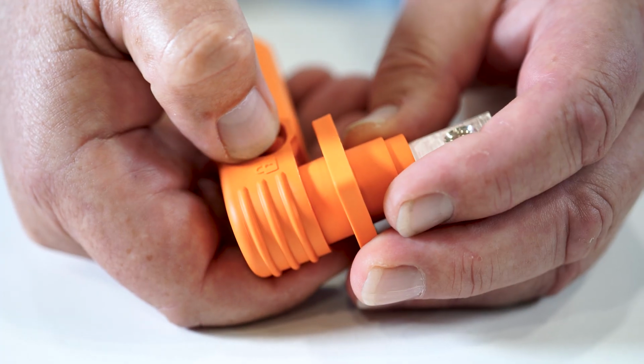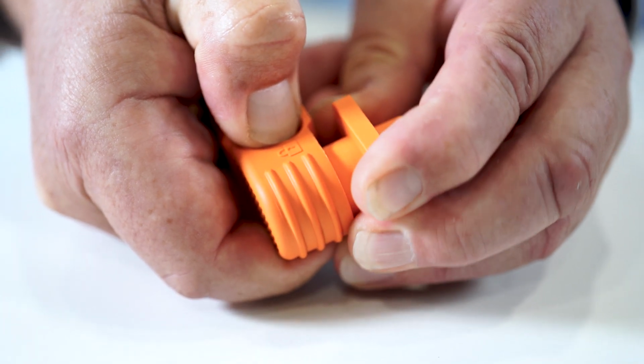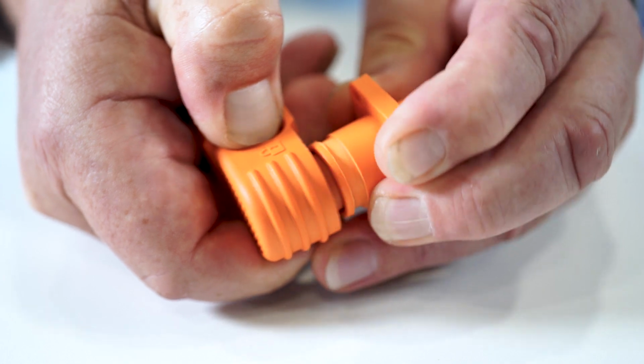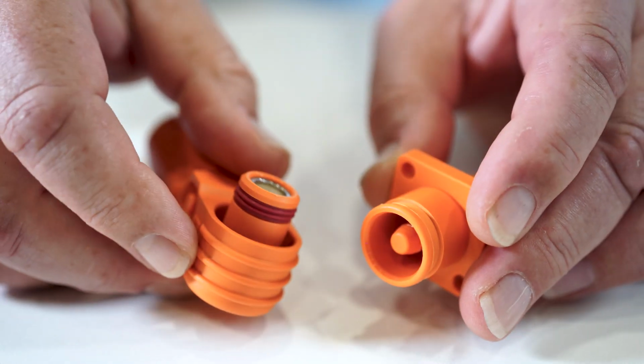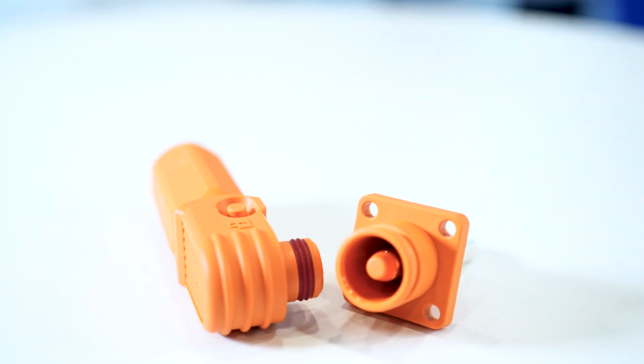Because of the many environments they're used in, the IP rating becomes very important. Some of these environments are quite harsh, where there may be liquids or dust ingress. These connectors are IP65 when unmated, meaning they're completely protected against dust ingress and water spray. However, when mated, due to the design of the connectors and the gaskets, they become IP67, meaning they're completely protected against dust ingress and can technically be submerged underwater up to 1 meter.